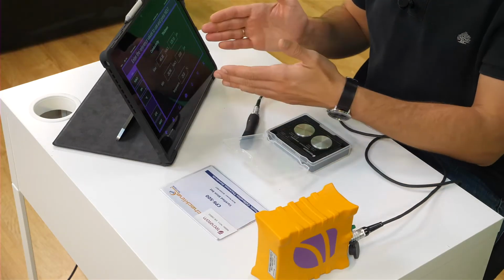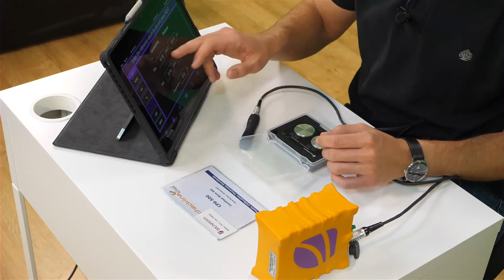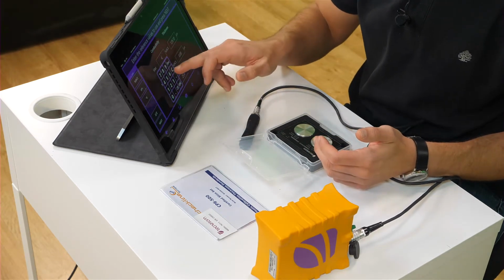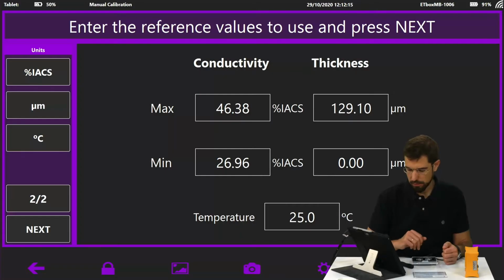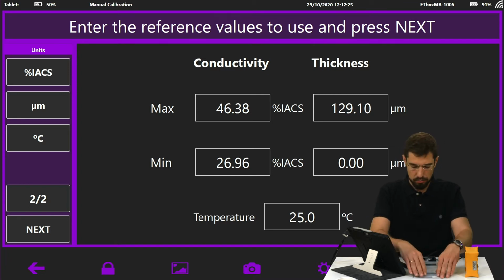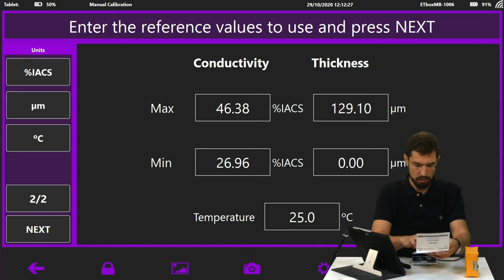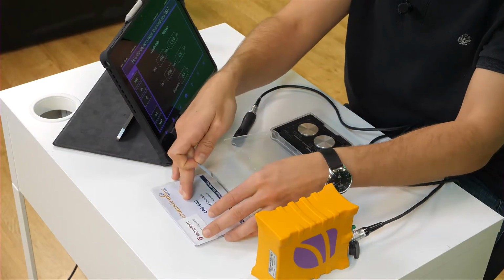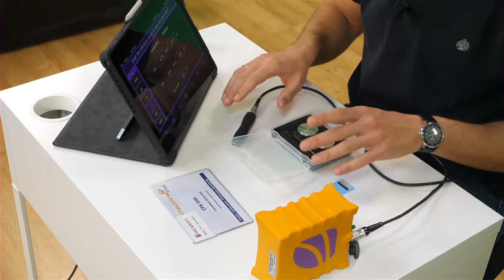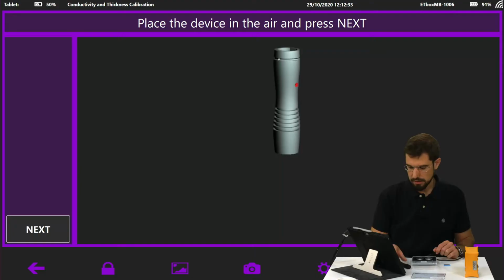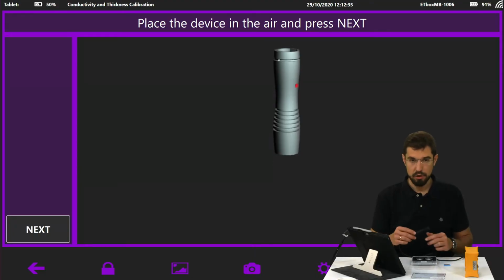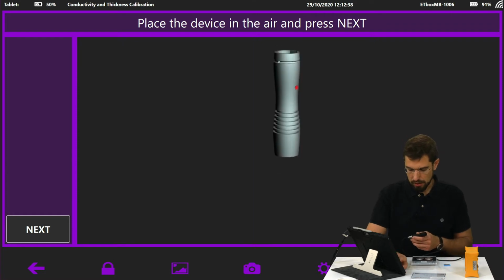Okay, so once we introduce the conductivity and thickness values of the patterns we're going to use to calibrate, in this case, I had already pre-charged them, but their tactile insertion is very easy. One is 26.96 and the other 46.38. And for the thickness measurement, we're going to do it between a zero gauge, that is, with no gauge, and a medium thickness of 129.1 microns. Once we have everything ready, we click on Next, and the software is going to guide us directly through the steps we need to follow.